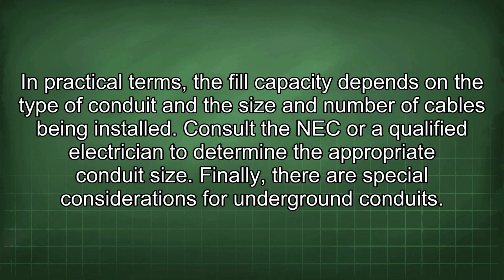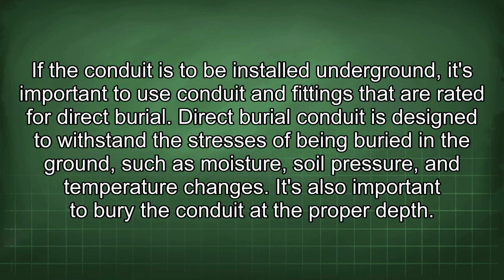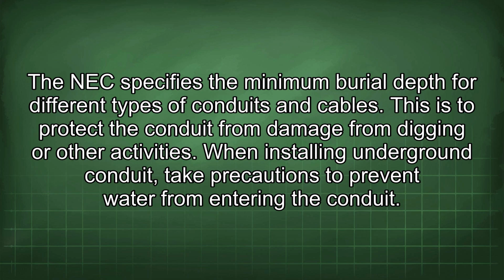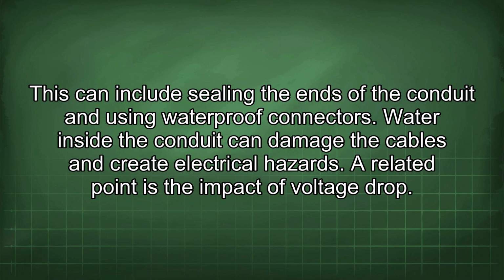Finally, there are special considerations for underground conduits. If the conduit is to be installed underground, it's important to use conduit and fittings that are rated for direct burial. Direct burial conduit is designed to withstand the stresses of being buried in the ground, such as moisture, soil pressure, and temperature changes. It's also important to bury the conduit at the proper depth. The NEC specifies the minimum burial depth for different types of conduits and cables. This is to protect the conduit from damage from digging or other activities. When installing underground conduit, take precautions to prevent water from entering the conduit. This can include sealing the ends of the conduit and using waterproof connectors. Water inside the conduit can damage the cables and create electrical hazards.